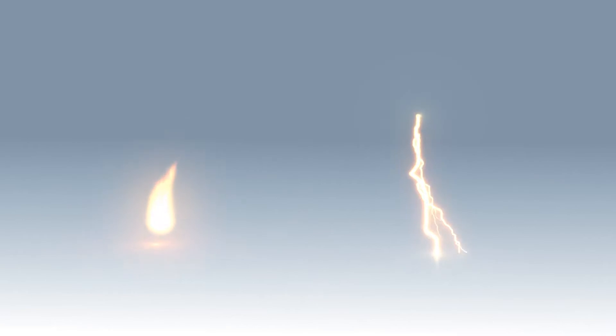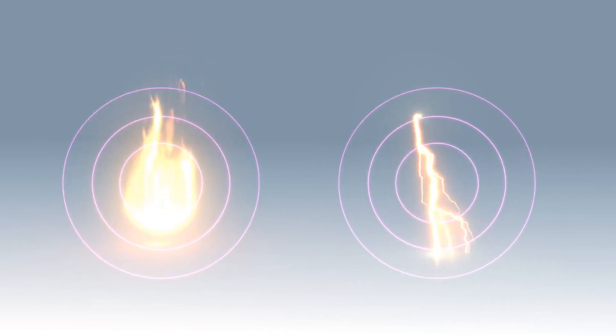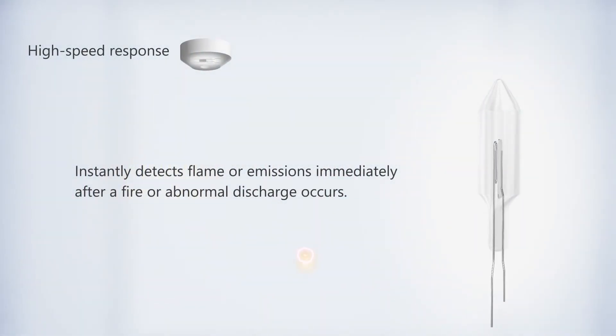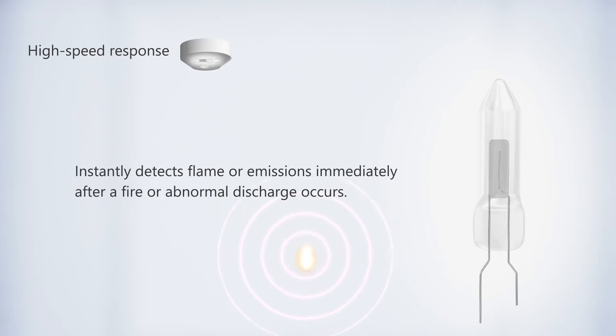Flames and electrical discharges constantly emit weak UV light. UVtron is highly sensitive to this weak UV light so that it can instantly detect flame or emissions immediately after a fire or abnormal discharge occurs. These weak flame and discharge emissions are usually difficult to detect with ordinary smoke and heat detection devices.